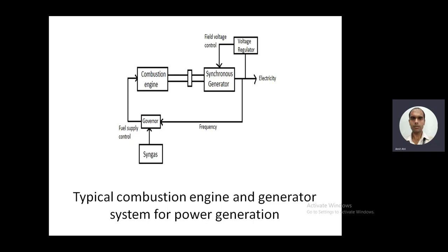the resulting change in the frequency will cause the governor to change the fuel supply to the combustion engine, so that the change in the generated output matches the power demand. In this way, the system frequency is also maintained constant.